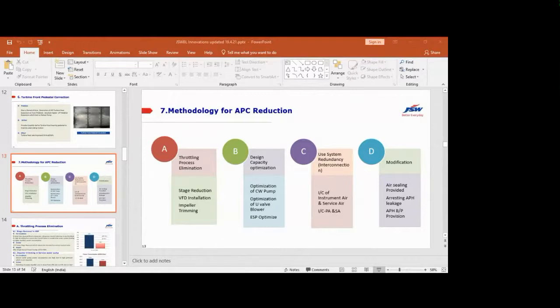So the methodology for APC reduction is throttling process elimination, design capacity optimization, and system redundancy modification. For throttling process elimination, the practices are stage reduction, VFD installation, and impeller trimming. For the stage removal in CEP, our CEP has 8 stages and the pressure was 22 kg, which was higher than required.